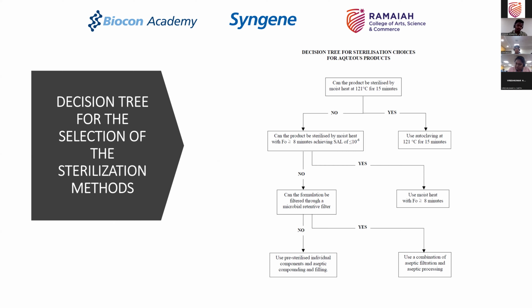So the first question which has to be asked when selecting a sterilization method is, can the product be sterilized by moist heat at 121 degrees centigrade for 15 minutes? If the answer is yes, then use autoclaving: package it in a container and then put it into an autoclave or terminal sterilizer for your sterilization process. So this is the first question to ask.